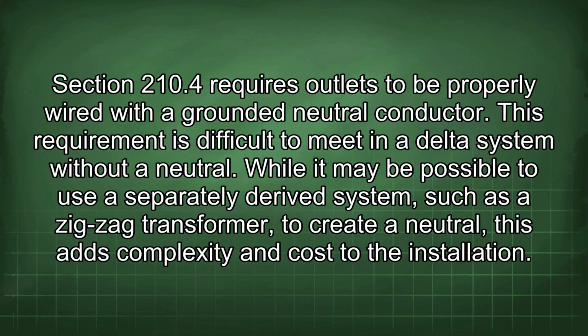Section 210.4 requires outlets to be properly wired with a grounded neutral conductor. This requirement is difficult to meet in a delta system without a neutral. While it may be possible to use a separately derived system, such as a zigzag transformer, to create a neutral, this adds complexity and cost to the installation.